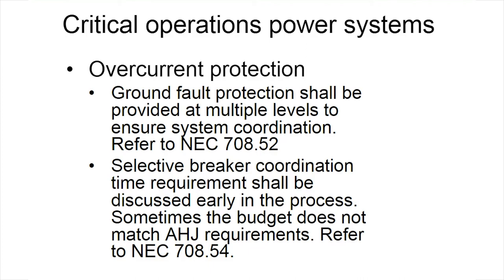Selective breaker coordination also should be discussed early in the process. I've seen many questions about whether you have to do selective breaker coordination on 501 for a hospital, in a different kind of building and so on. No, selective breaker coordination is only for the emergency circuit and wherever it's described in the code, like on hospital, on 517, I believe. So if it's not one of those, you don't have to do it.